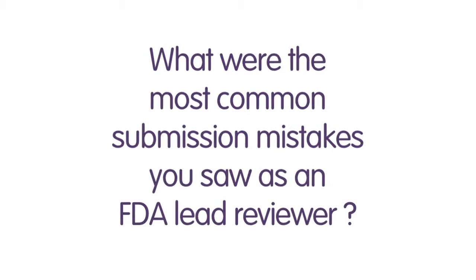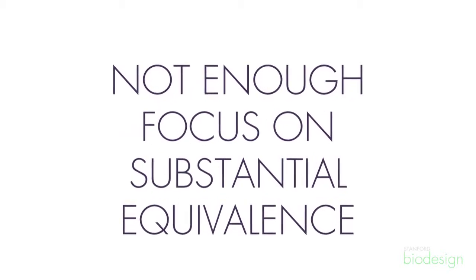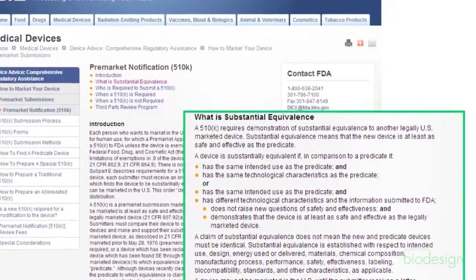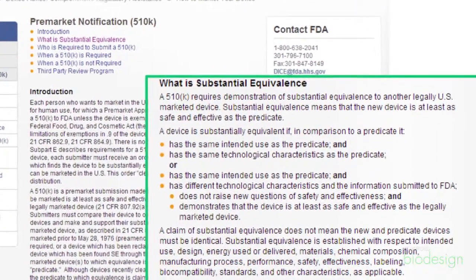As an FDA lead reviewer, some of the most common mistakes that I've seen when reviewing 510Ks is not putting enough focus on demonstrating substantial equivalence to your predicate — that's your aim. I actually think that's one of the more challenging things to do, because from a marketing perspective, or even in your own eyes, you're trying to innovate a new medical technology and distinguish yourself from technology that currently exists. With that mindset, it's difficult to put yourself in a mode to demonstrate that you're equivalent to something else.